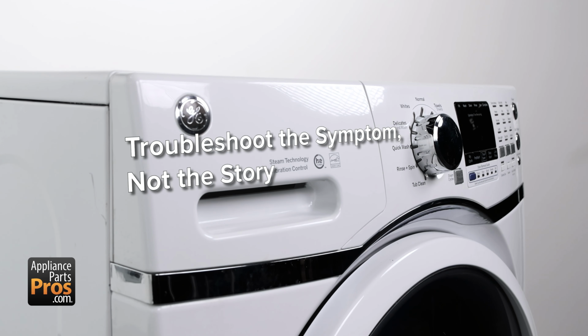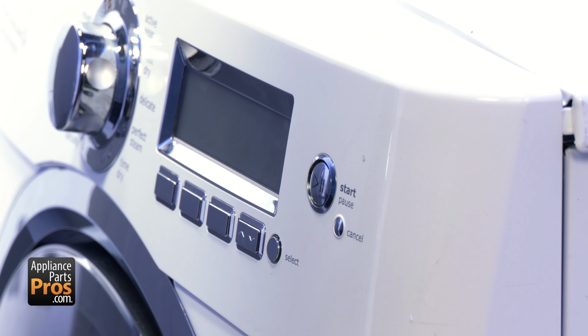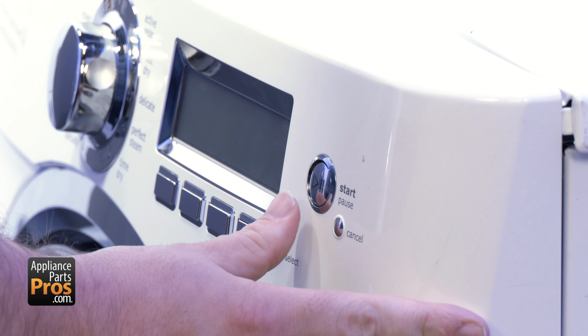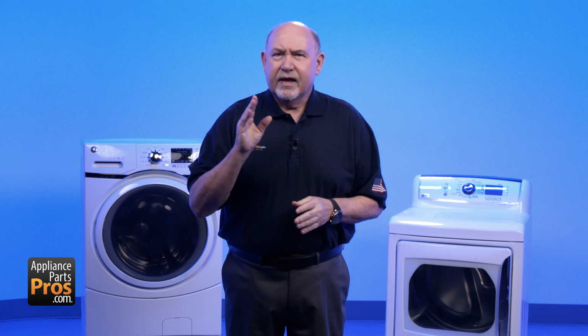Before meters, before panels, before ordering anything, get painfully specific. Not, it won't start, more like the display turns on. I press start, it clicks once, then nothing happens. Not cooling, more like freezer is warm. Evaporator fan is running. Compressor is hot to the touch. Condenser fan is silent. Specific symptoms shrink the search area. Vague ones explode it. And while you're here, try the easiest recreation possible. Same settings, same conditions. Intermittent problems love to hide behind randomness.